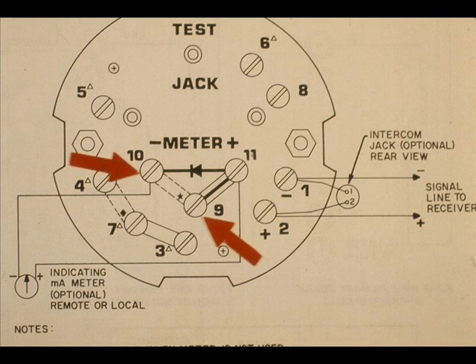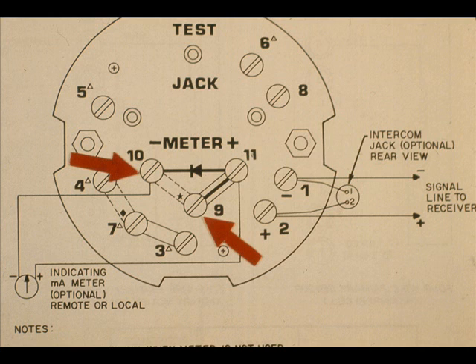Means are provided for the installation of a local plug-in type meter if desired. The upper metal link is connected from the center to the positive side of the meter terminals when a meter other than the plug-in type is used. This is terminal 9 to terminal 11. The link is connected from the center to the negative side of the meter terminals when either no meter or the plug-in type is used. This is terminal 9 to terminal 10.